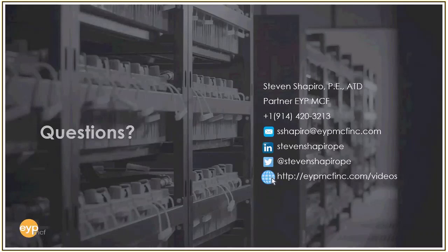Thank you. The battery monitoring system identified 10 to 20% bad or weak batteries of the total number of batteries in a large UPS system. Do you advise to mix new with old batteries, especially for mid-age batteries? So that's always an issue. Ultimately, it's not cost effective to replace the entire string of batteries when you have a couple of bad batteries. We've typically provided spare battery racks and cabinets when we do new installations, so that if we end up with, in 3 or 4 years on a flooded cell battery, if we notice we have a bad battery, we have a spare to replace it that's of the same age. Not necessarily the same number of discharge cycles, but at least it's the same age and the same type of battery, and we can replace those. But once you get above, I would say probably 20%, once you know you've got 20% bad batteries, you're probably looking at a full replacement of the battery string.